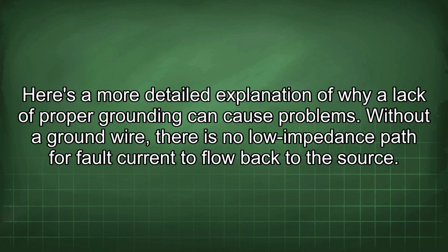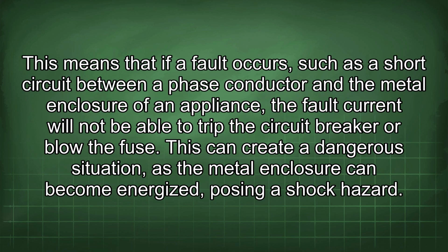Here's a more detailed explanation of why a lack of proper grounding can cause problems. Without a ground wire, there is no low impedance path for fault current to flow back to the source. This means that if a fault occurs, such as a short circuit between a phase conductor and the metal enclosure of an appliance, the fault current will not be able to trip the circuit breaker or blow the fuse. This can create a dangerous situation, as the metal enclosure can become energized, posing a shock hazard.